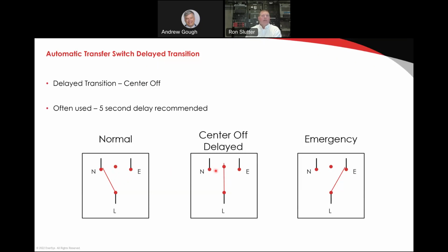Okay. So the switch will move from normal to the center off position and then ultimately from the center off position to emergency based on the programming that's in the ATS. Once again, this switch eliminates the problem of having a transient response on the return from emergency because it will be programmed to sit on the center off spot until that load source has no voltage. And then based on the delay, which is typically around 5 seconds, it will transition to normal and pick up the new source. And that eliminates the transient that can be generated by switching directly between two different sources.